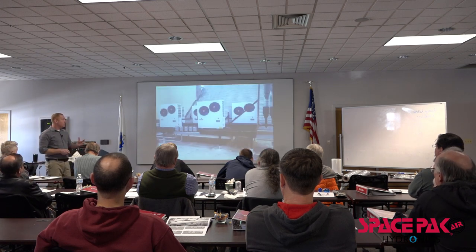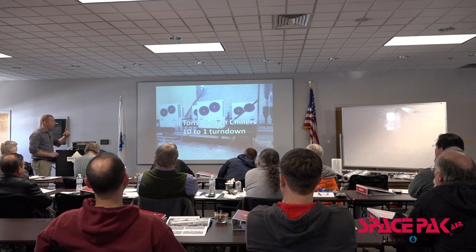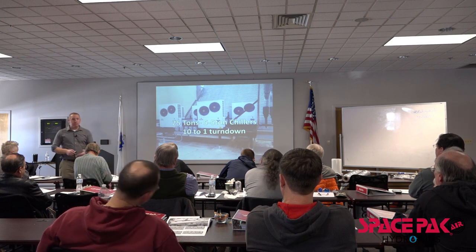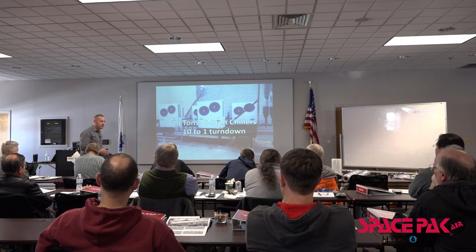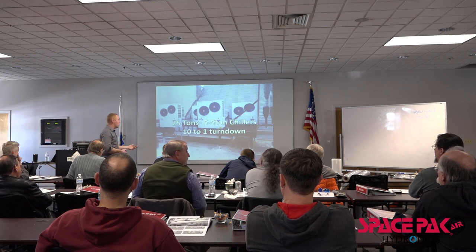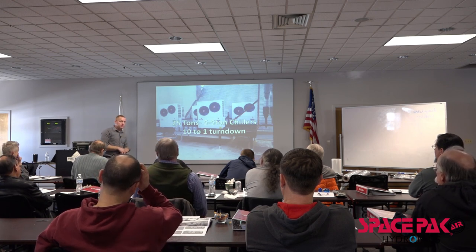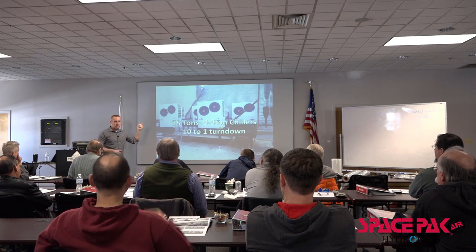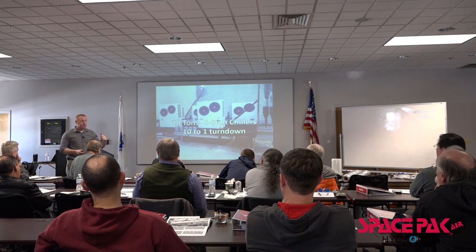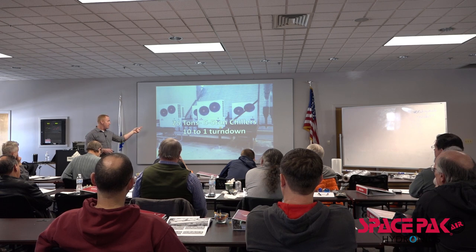Now, five units here. This was a church. I think this was in Maryland. They had one 25-ton chiller, and they needed cooling. I haven't checked the price tag on a 25-ton chiller, but I can imagine it's relatively expensive, right? So they said, geez, we pass the plate a few more times, we get some more donations, and they started buying heat pumps, our 5-ton units. So now they've got enough to cool it when the place is full, and they have the redundancy to, guess what, shut them off when we don't need them.